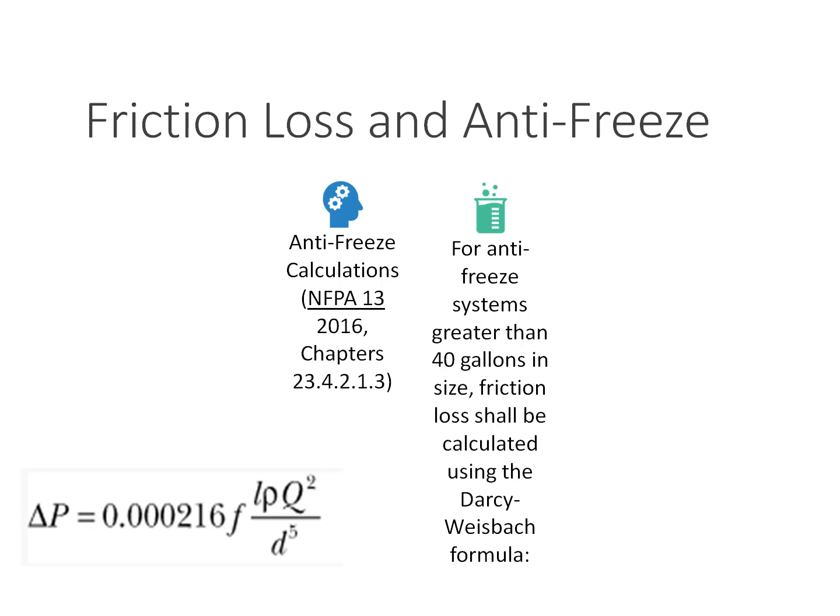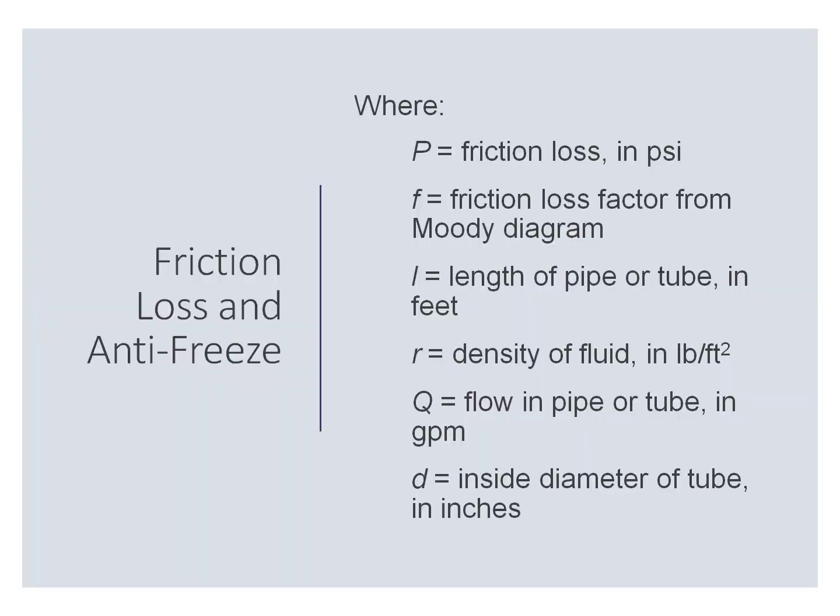Section 23.4.2.1.3 references antifreeze calculations. For antifreeze systems greater than 40 gallons in size, friction loss shall be calculated using the Darcy-Weisbach formula.